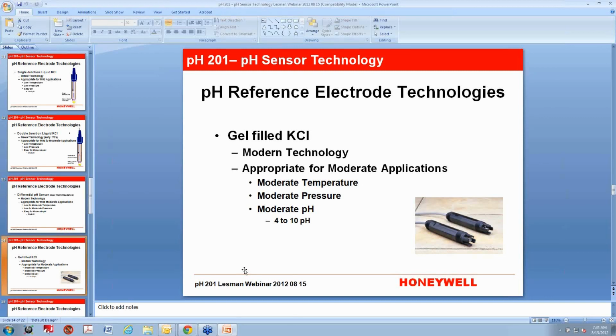Not all gels are created equal. Some gels don't do well with elevated temperatures and pressures. Some do better. I can tell you that the gel in some of the Honeywell sensors that use the gel technology is a gel that will not change viscosity throughout the whole temperature range of the sensor. But some gels do change, so you want to keep an eye on that if you're going to use a gel technology. Again, this is the most common technology, and it's appropriate for moderate applications, so medium temperatures and a moderate pH, say 4 to 10.